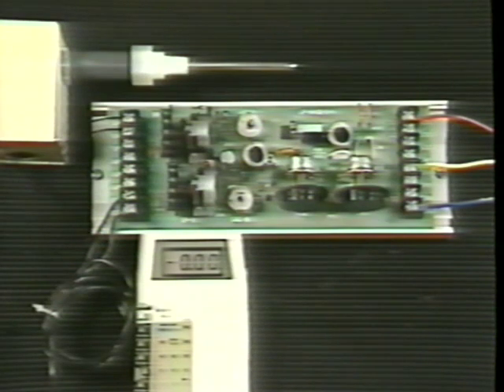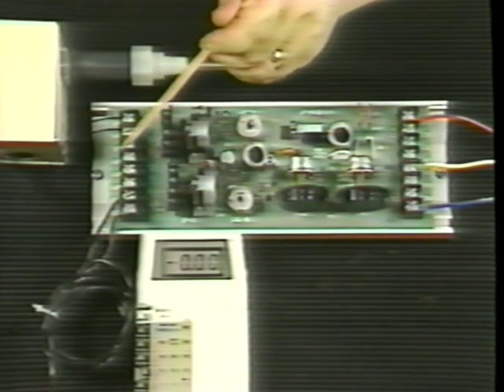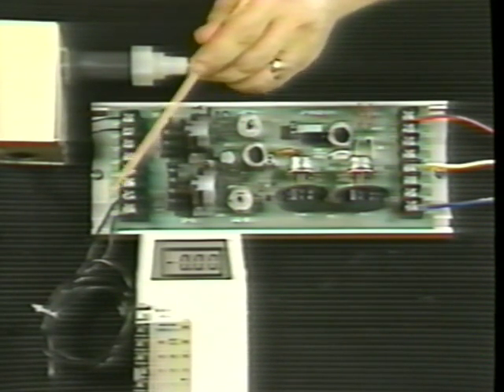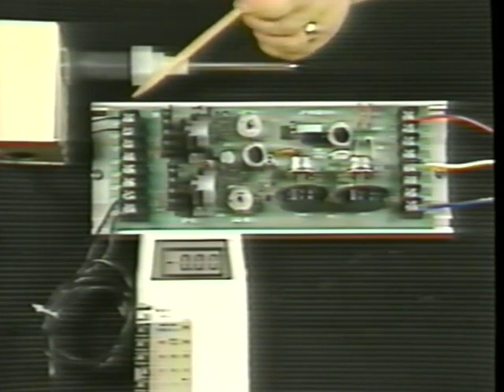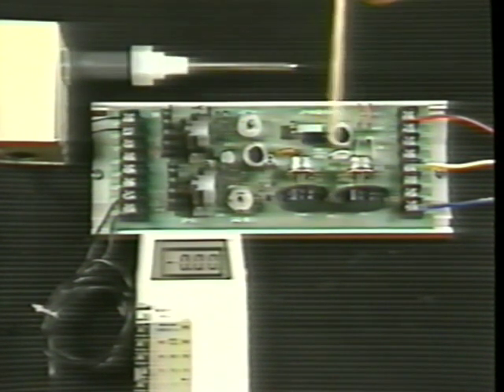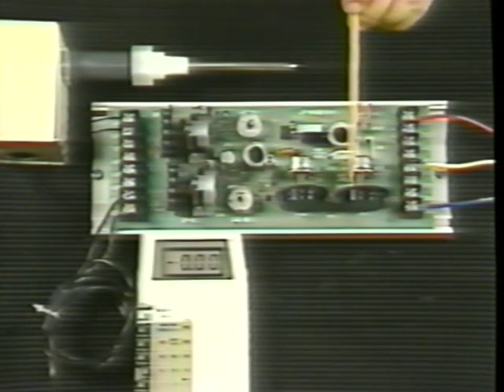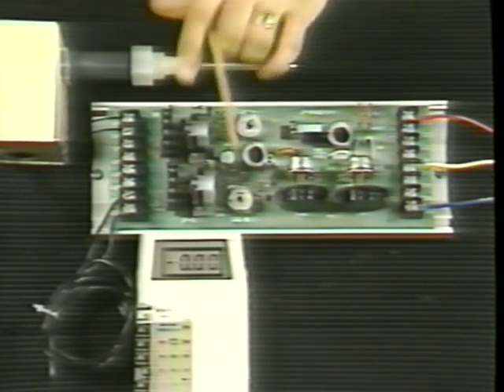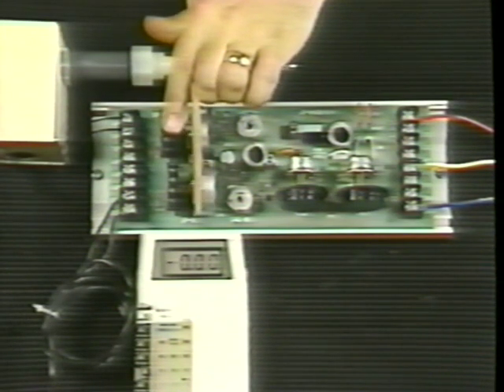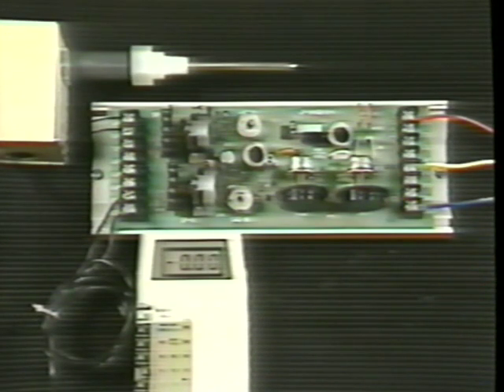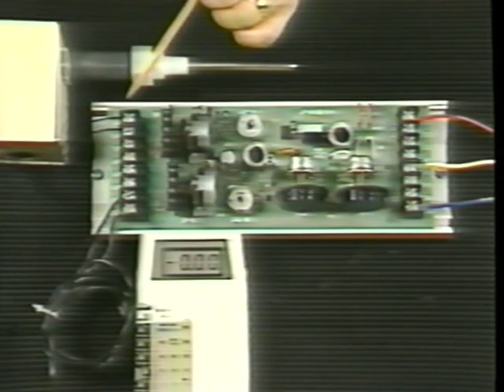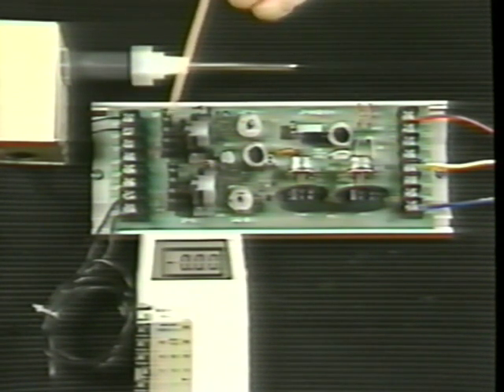Applying these rules to the CP8102, if an auxiliary bridge and/or input B are being used, disable them and then begin calibration with input A. Adjust the throttling range to the desired value for the application, or if not yet known, adjust to 3. Measure the variable at A and adjust the set point equal to it. If for any reason this is not possible, replace the sensor with a precision plus or minus 1% 1000 ohm resistor and set the set point equal to 70 degrees Fahrenheit.